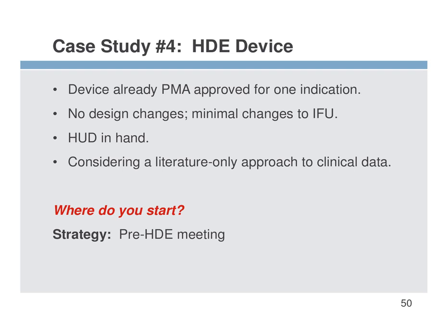And again, as far as de novo or PMA product, I might suggest that if you're firmly convinced it's not a 510K, then you might just say in your introductory cover letter, hey, here's our product, we're submitting it via de novo, but in the meantime we have some questions. But if you think it's a de novo, they'll probably want to have a de novo meeting to discuss it. So that would be one of your first questions. I hope I answered that question well enough. There seems like there might be more there. Hey, the company is not fully clear. Feel free to ask a follow-up question.